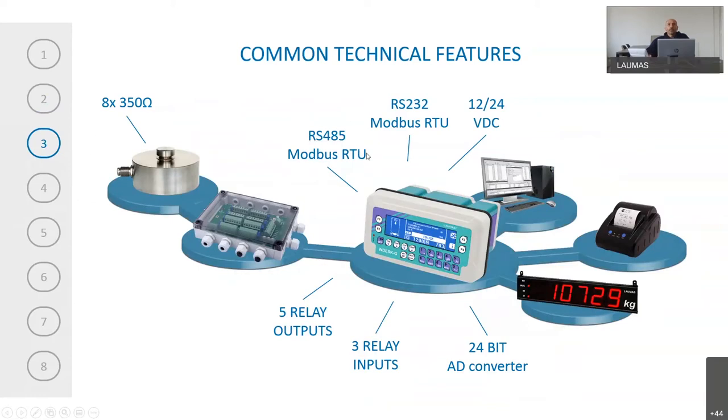Here we can see the common technical features of LAUMAS indicators. You can connect up to eight load cells with 350 ohms. You can have one serial port RS-232 and one serial port RS-485 with Modbus RTU protocol. We can have five integrated relay outputs and three integrated digital inputs.